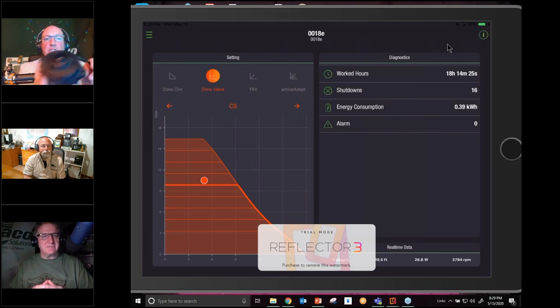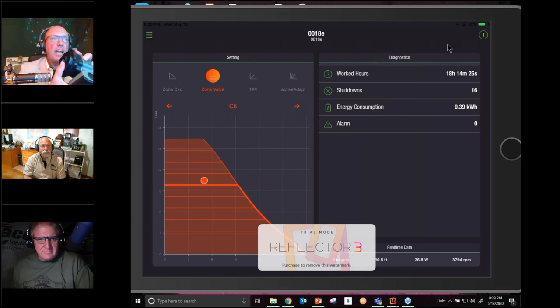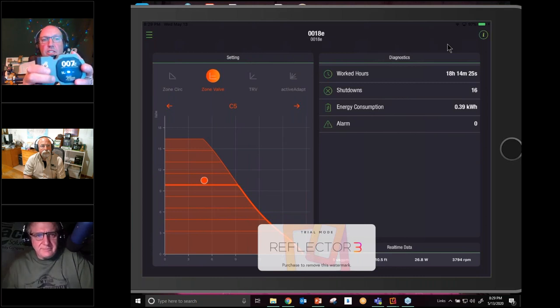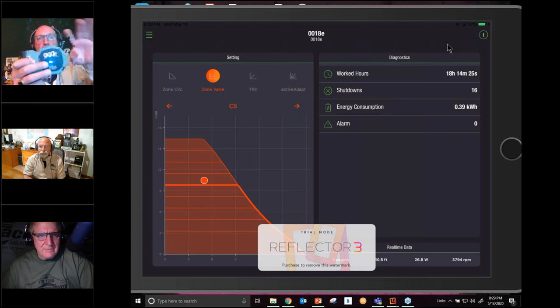I've got a circulator here that I've put a cord on, and I've got a power supply and a switch, and I'm going to hold the impeller. I pulled the casing off of here. So if I turn this thing on, it's going to try and run. You're going to see the light under normal operation ramps up the speed. It's not going anywhere. I'm holding it tight with two thumbs on it. It stops. You get a red and a white flashing light, which means, all right, I'm going to shake it back and forth and then go up to full speed.